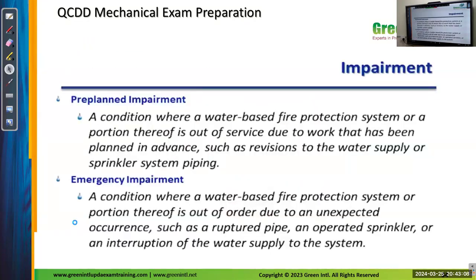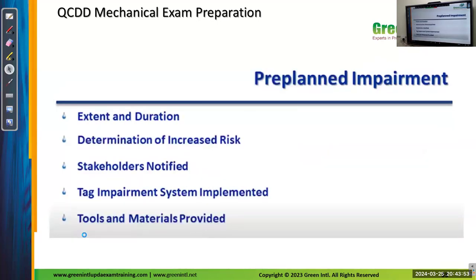What is impairment? Impairment is a technical term for replacement of that part or to undergo some repair works. Pre-planned impairment is a condition where a water-based fire protection system or a portion of it is out of service due to work that has been planned in advance, such as revision to the water supply or sprinkler systems. Means it is like maintenance. Emergency impairment is a condition where a water system is out of order due to an unexpected occurrence or rupture. These are all the definitions for these terms.